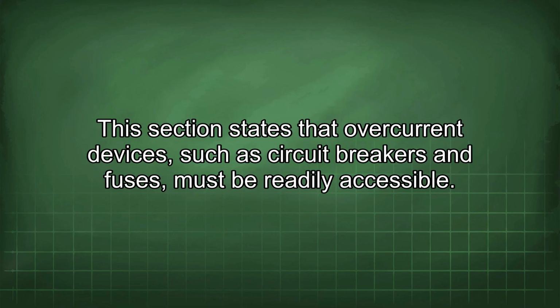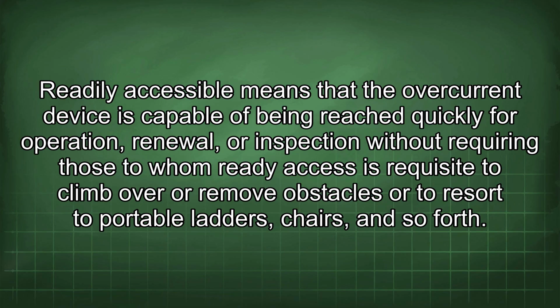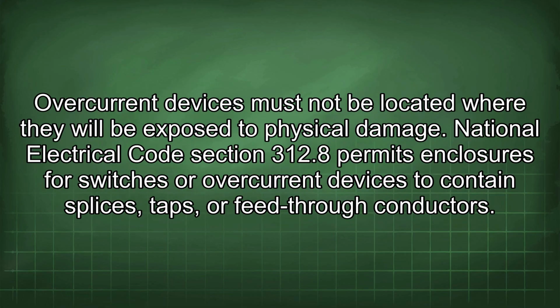This section states that overcurrent devices, such as circuit breakers and fuses, must be readily accessible. Readily accessible means that the overcurrent device is capable of being reached quickly for operation, renewal, or inspection without requiring those to whom ready access is requisite to climb over or remove obstacles or to resort to portable ladders, chairs, and so forth. Overcurrent devices must not be located where they will be exposed to physical damage.